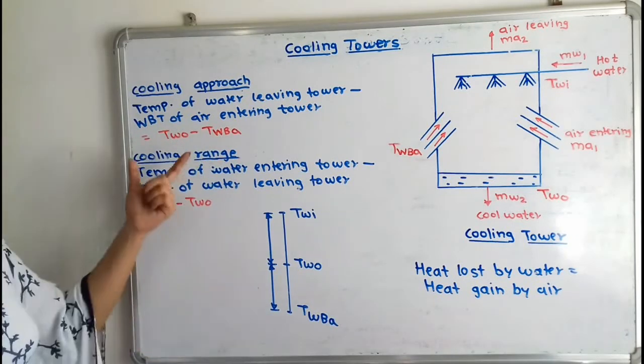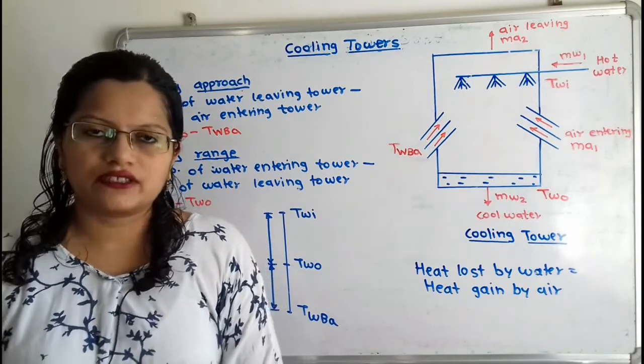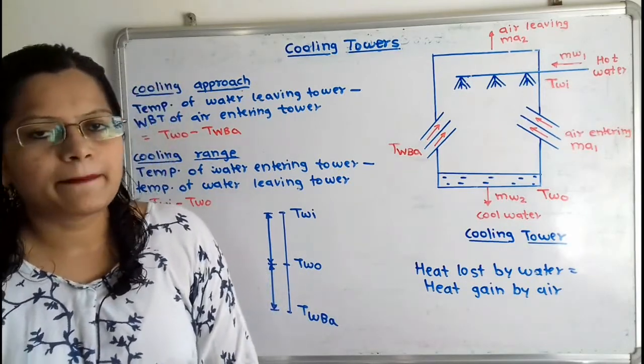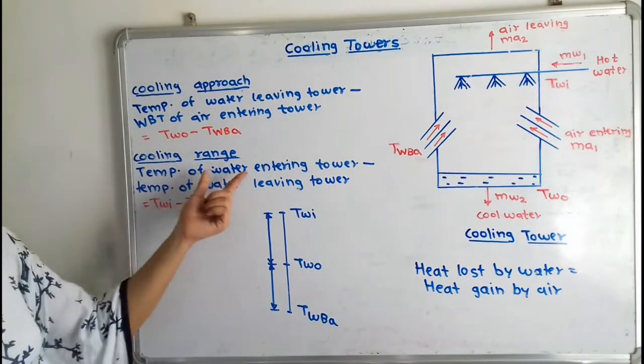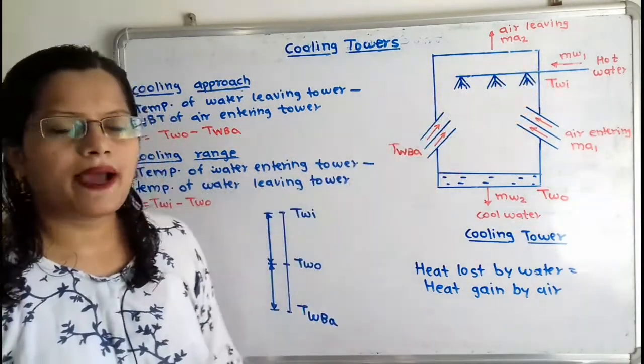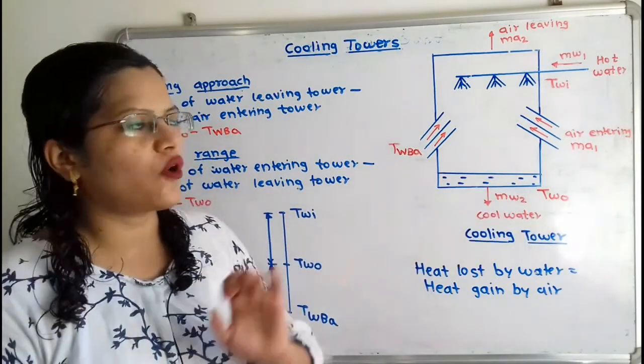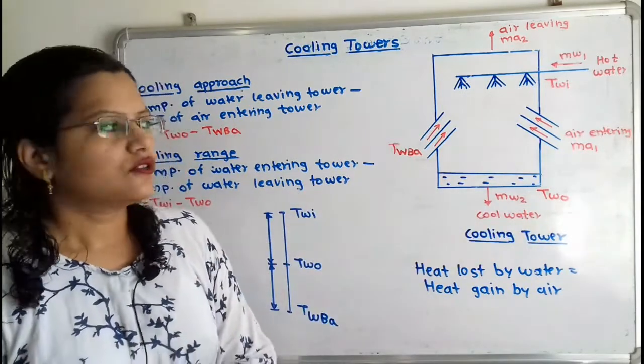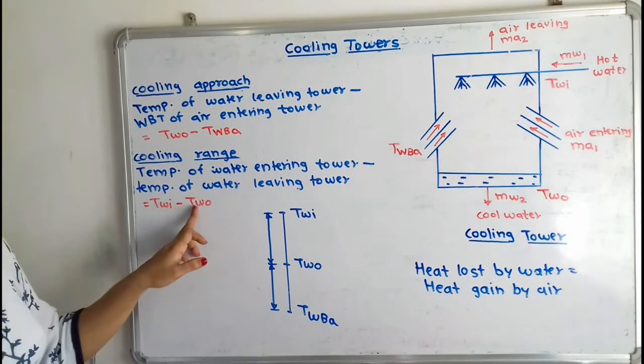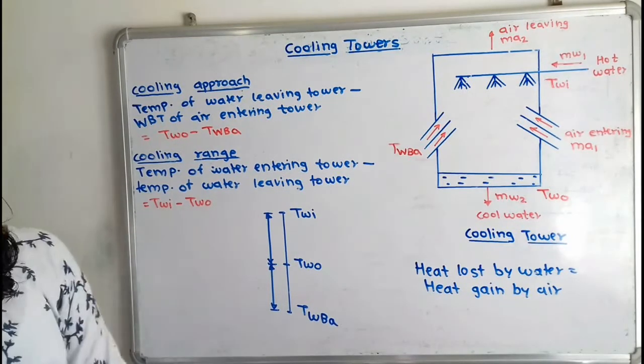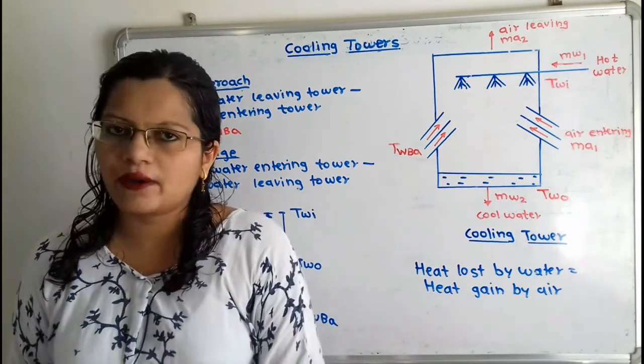The next parameter is cooling range. This is also a temperature difference: the temperature of water entering the tower minus the temperature of water leaving the tower. So cooling range equals TWI minus TWO. Now we will understand this with the help of a diagram.